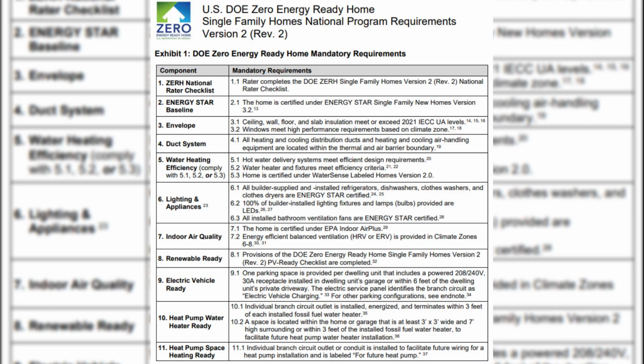10. Heat pump water heater ready. Every fossil fuel water heater must have a dedicated circuit installed within 3 feet, and enough clearance, at least 3 by 3 feet, 7 feet high, to allow a future heat pump water heater to be added. 11. Heat pump space heating ready. And finally, the home must include a branch circuit or conduit for future heat pump installation. It needs to be labeled clearly as, for future heat pump. This future-proofs the home for electrification.